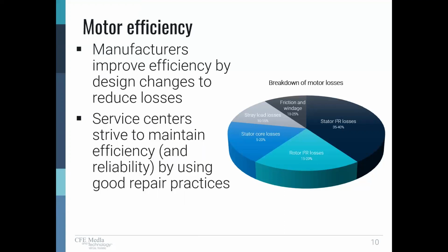And then the final area, stray load losses. If we went back a century ago, the motor designers at the time knew, by doing testing for motor efficiency, that there was more to motor losses than what they could calculate.